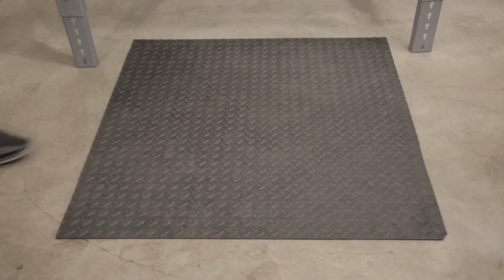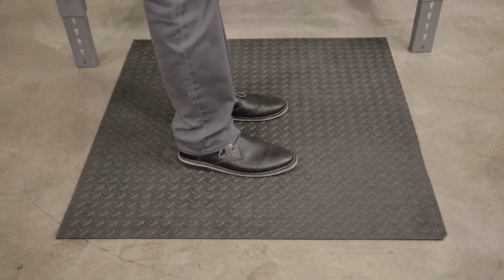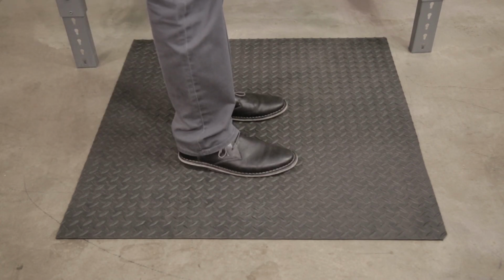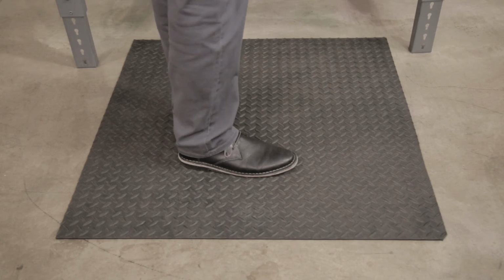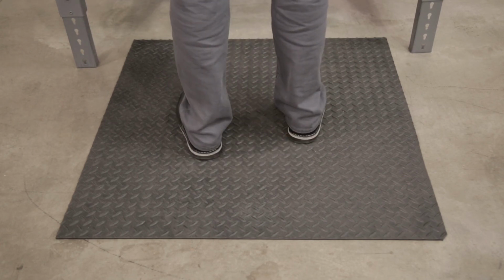The insulation mat protects the test operator from electrocution by isolating the operator from ground. If the test operator comes in accidental contact with a high voltage output, the insulation mat will not allow a path for the current to flow through the operator.